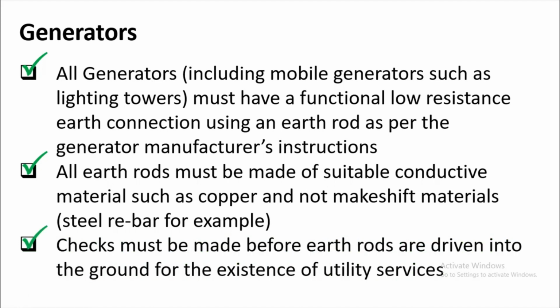Checks must be made before earth rods are driven into the ground for the existence of utility services. So before we drive the earth rods into the ground, make sure that there are no utility services there or that it is far away from them, because you might hit those services if you did not verify it. So again, the electrician should verify the as-built drawings of the location, and if you have cable detectors, you can run them on that location, so that you make sure that your earth rods will not hit any utility services on that particular location.